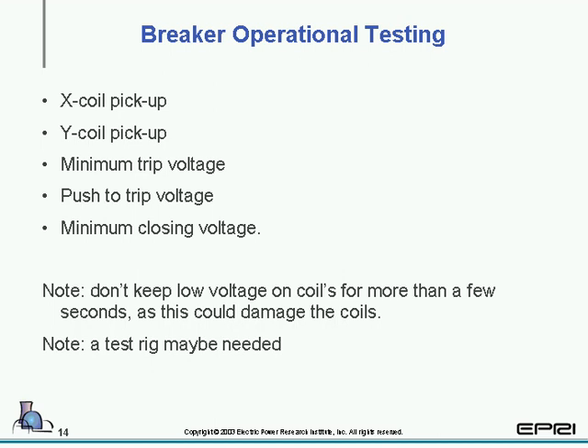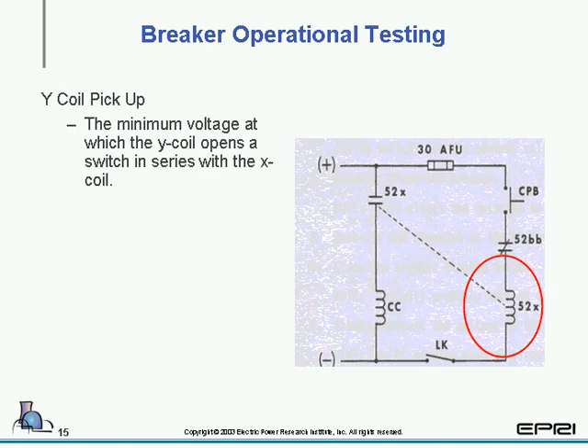We're also going to take a look at breaker operational testing, and then we're going to take a look at what we just spoke about. Now they can be done to all the tests, all the coils that are actually within the breaker. The X coil, the Y coil, you can do the minimum trip voltage, you can do pushed trip voltage, minimum closing voltage, and again, do not keep the voltage on these coils for long periods of time.